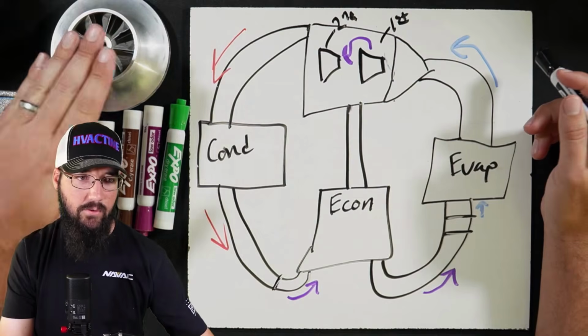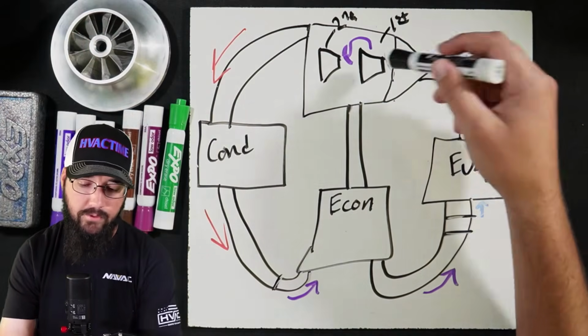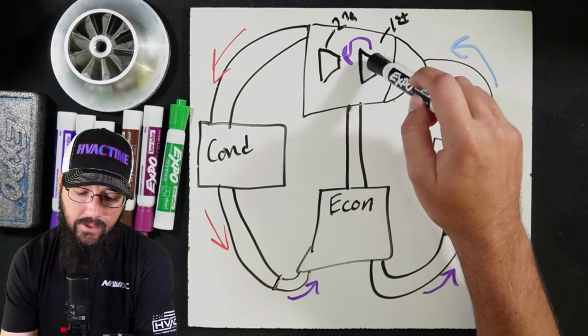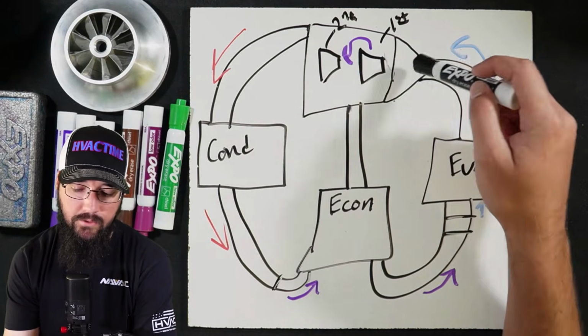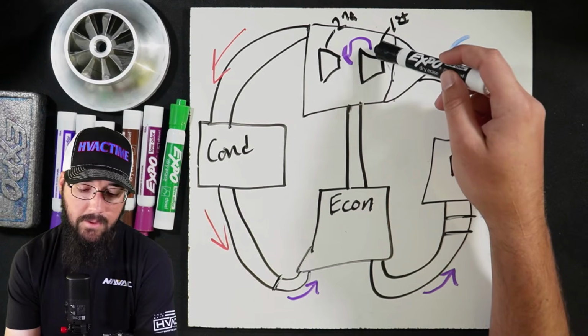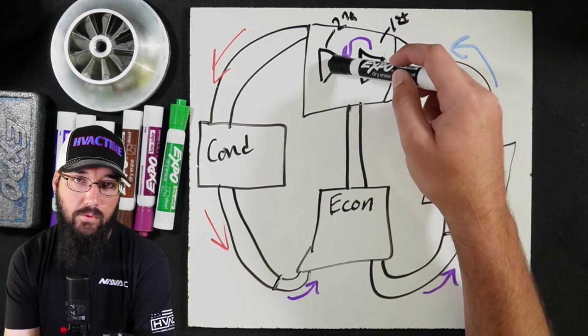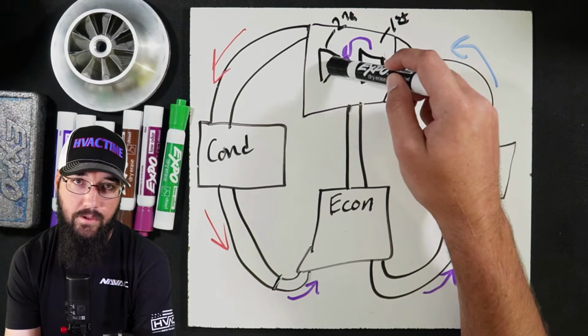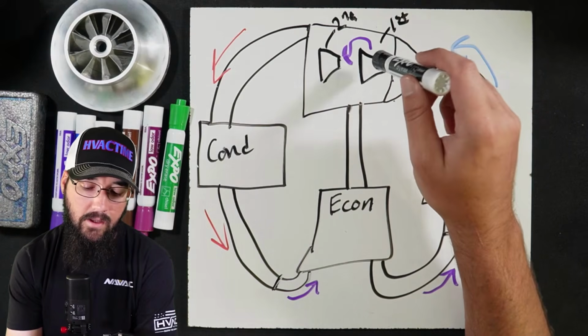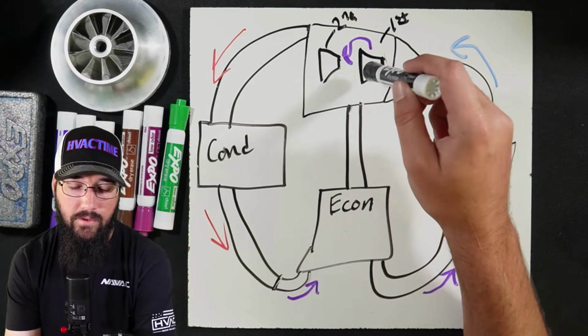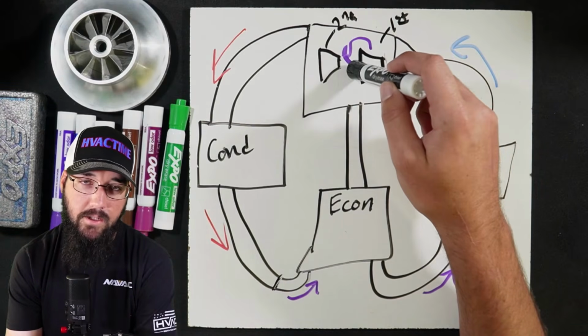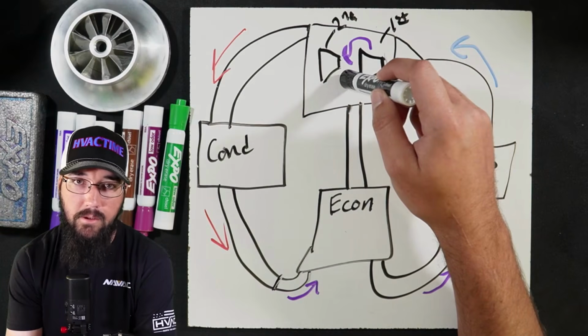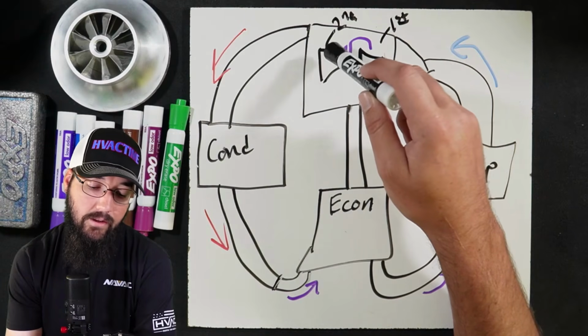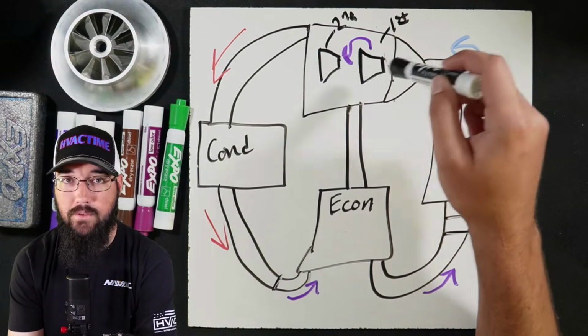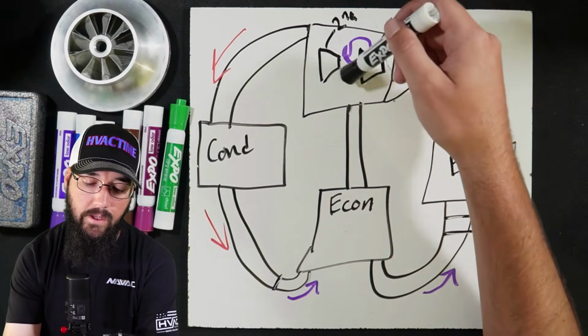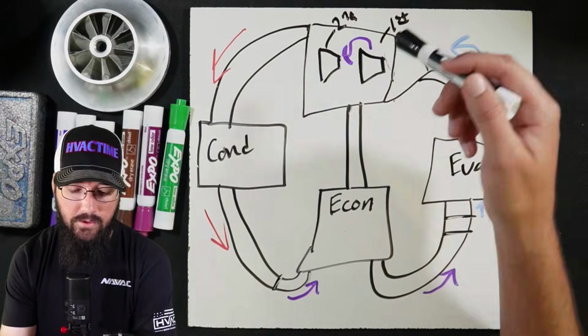So we've got a set of vanes that are basically just paddles that are controlling the refrigerant coming in. This impeller takes a refrigerant to a medium pressure. So we go from low pressure to medium pressure. That medium pressure then gets fed into the second impeller, which goes from medium to high pressure. So it's a two-stage cycle on this. If there are three impellers, we go from low pressure to medium low, to medium high, and then medium high to high pressure. So that's your staging sequence for a three-stage versus two-stage machine.